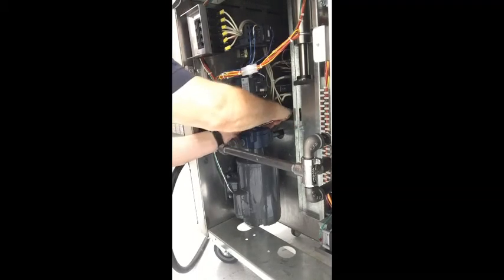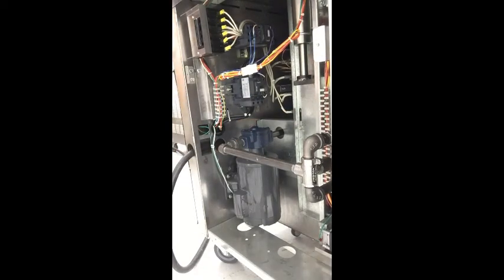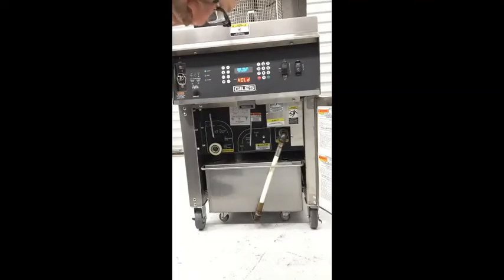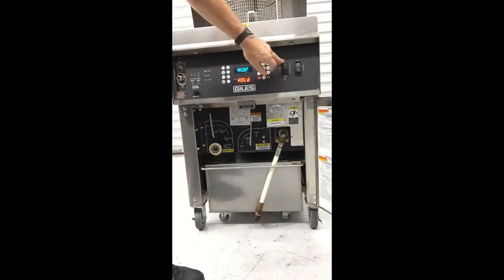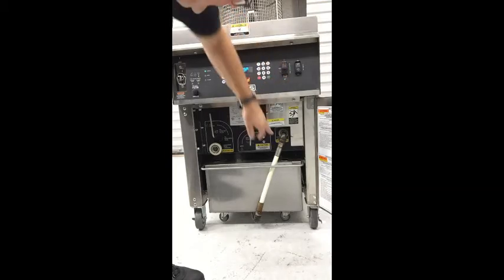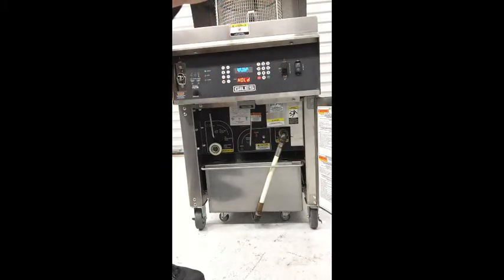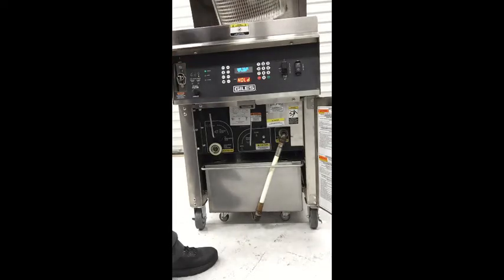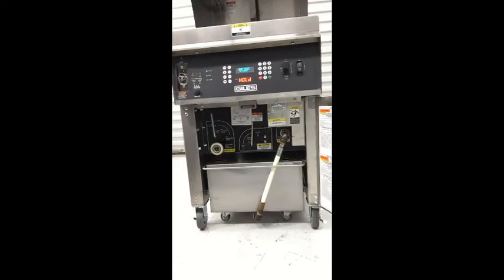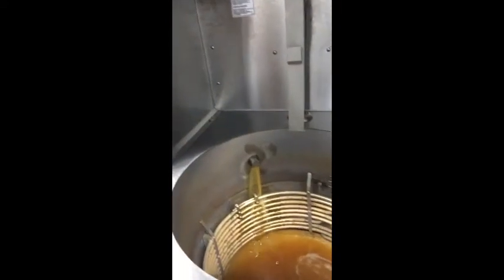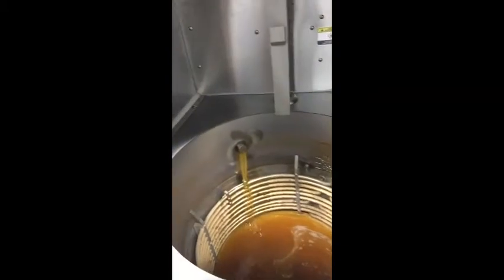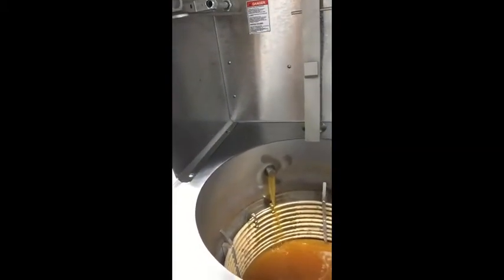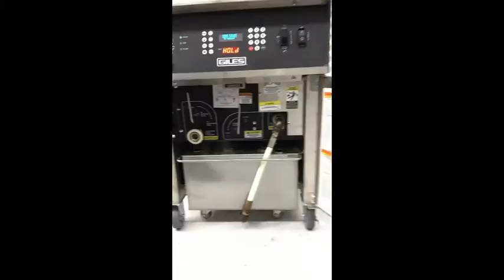We don't want to let the pump run dry for long, so we want to do this in a fairly quick motion. I'm going to go ahead and turn the unit back off. Okay, now we can go back around the front and see whether or not we've got this pumping. Okay, now that we've got the pump cleared out and it sounded like it was going to go, let's go ahead and turn the pump on. Let's see if we've got success. Coupled up. Sounds like magic. All right. We'll take the basket out. And you can actually see the oil returning right here, coming back into the fry pot. Okay, we have the drain valve closed right now so that we can let that fill back up.